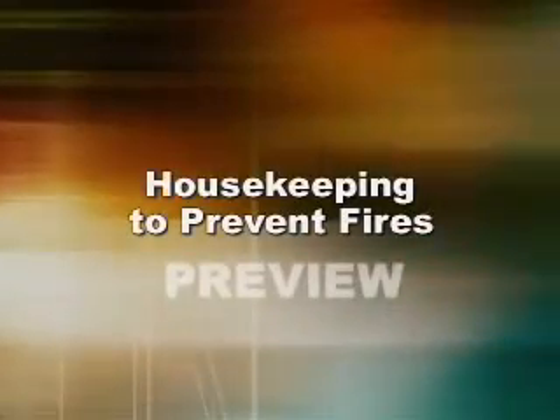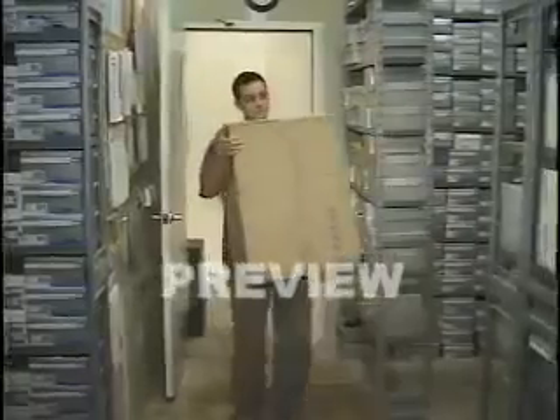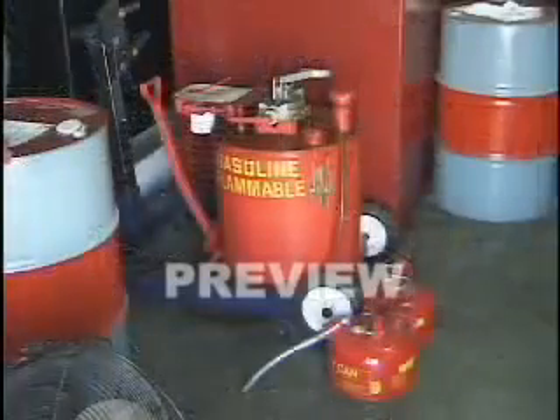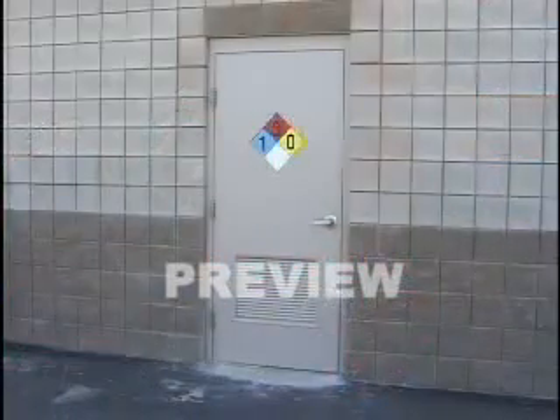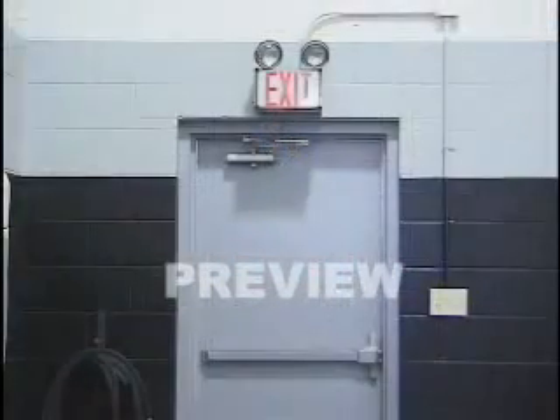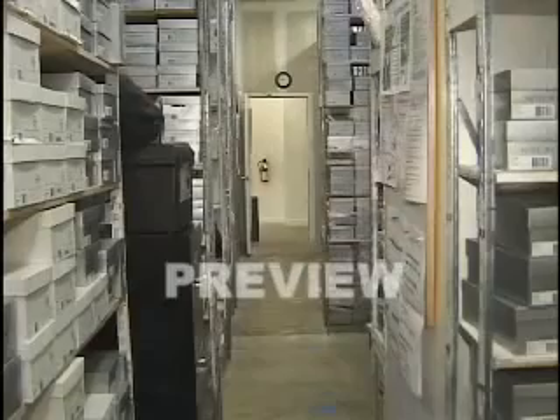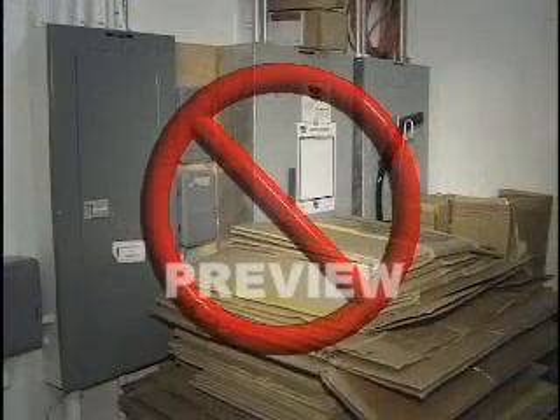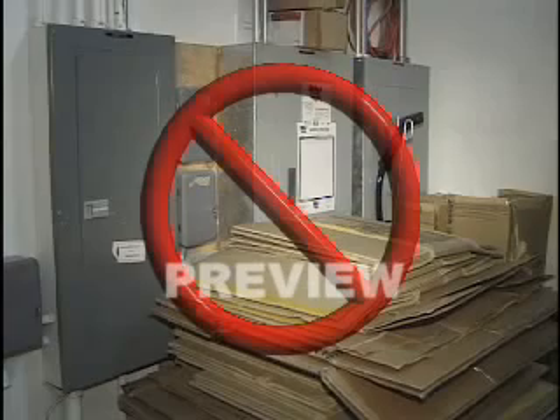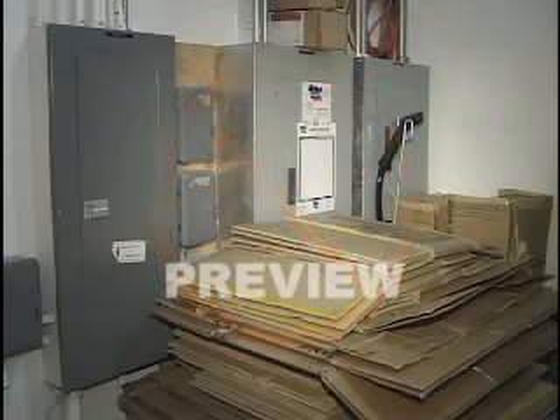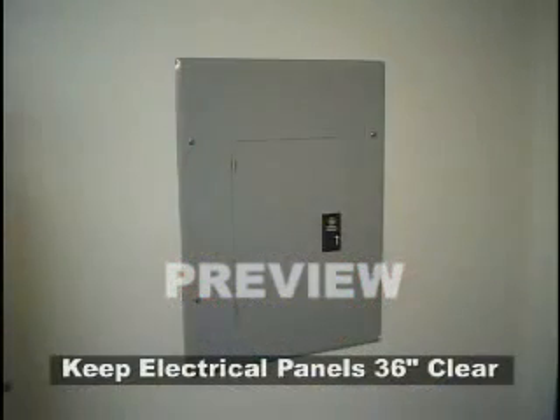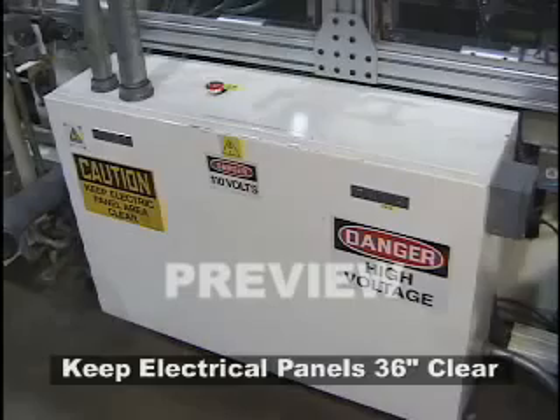Housekeeping to prevent fires. Good housekeeping ties in closely with fire prevention. If you allow debris or flammable material to accumulate, the risk of starting a fire increases. Keep equipment and materials in their proper locations, and make sure all exits, hallways, and corridors are kept clear. Not only is it a bad, unsafe work practice, but it's also a serious safety violation to block any emergency exits or electrical panels. In fact, fire codes require that they have 36 inches of clearance.